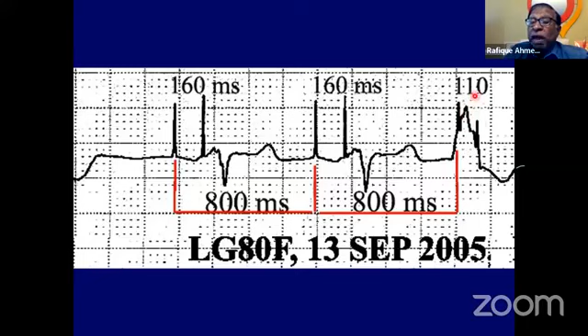What would happen is there is atrial pacing in a complete heart block patient, that spike is sensed by the ventricle and it inhibits the pacemaker. And there will be asystole despite the fact that the patient has a dual chamber pacemaker. To prevent that, it is incorporated in all pacemakers that if during the blanking period there is a sensed event within the programmed PR interval, any sensed ventricular event, it will pace the ventricle instead of inhibiting it. And it's called safety window pacing.